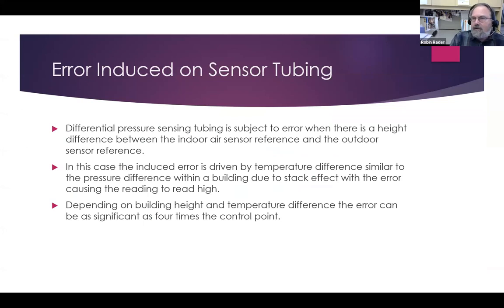So for static pressure sensors, there is an error induced in the tubing when the height of the outside reference point is different than the height of the indoor reference point. In this case, the error is driven by the outside pressure difference, or the difference between the outside air and the inside air due to stack effect. And it depends on the height difference and the temperature difference of the outside air, and it can be as significant as 4 times the control point.